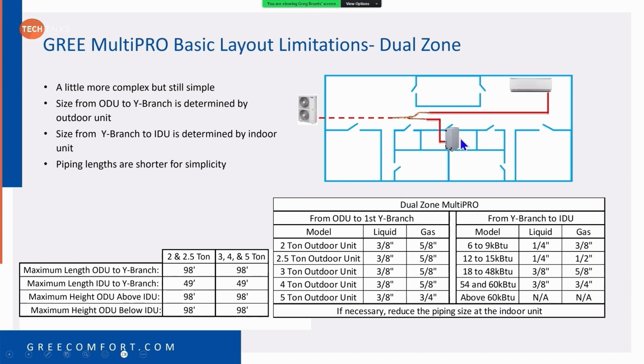So let's say this was a 2 ton air handler. I'd go down here, 18 to 48 is 3/8, 5/8. Let's say this is a 9K indoor unit here. I'd come down here. As long as I'm less than 50 feet or 49 feet, then my size pipe for there would be 1/4, 3/8 from here all the way to that indoor unit. And that's where I encourage you to try to locate this Y branch so that you're keeping these pipe lengths so you don't have to increase in size.